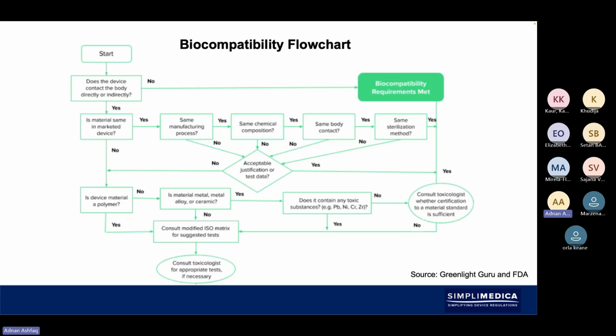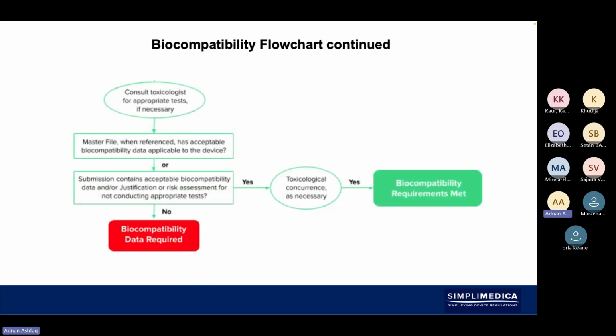We can also have a look at the materials to see if there's already material that's being used, which is FDA approved or is already used for human use or has been used in medical devices. So these are very important things to have a look at, which can reduce the burden, the workload that needs to be done. But ultimately, you need to have a look at the toxicological effects of any materials that are used in biocompatibility. And then you may be able to write a justification, or you might need to have specific tests done, especially if you've got novel materials, to meet those requirements.